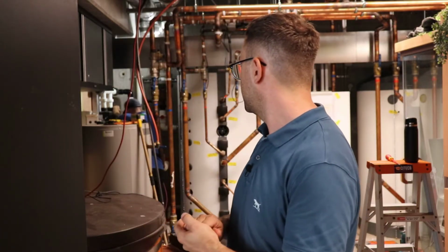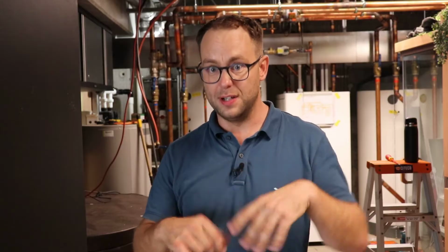So this is an open loop system, which means that we're quite lucky here in Perth. There's a lot of groundwater everywhere, so we can utilize this groundwater and either strip heat from it when we need it, or dump heat into it. That means we bring the water up, it goes through a heat exchanger, which you can't actually see right now but it's over there in the back corner. The groundwater and our system water go through, they exchange energy without mixing, and the groundwater goes back down.